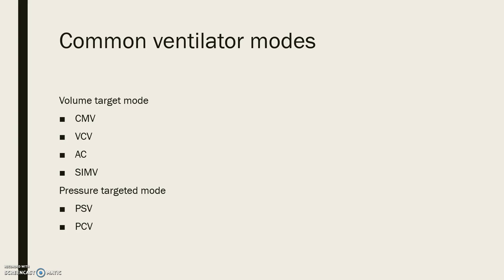There are several ventilator modes to meet the needs of the patient, with differentiation made between mandatory and spontaneous breathing methods. During volume-controlled ventilation, the set tidal volume is supplied by the ventilator at a constant flow. Both the tidal volume and the number of mandatory breaths per minute can be adjusted.